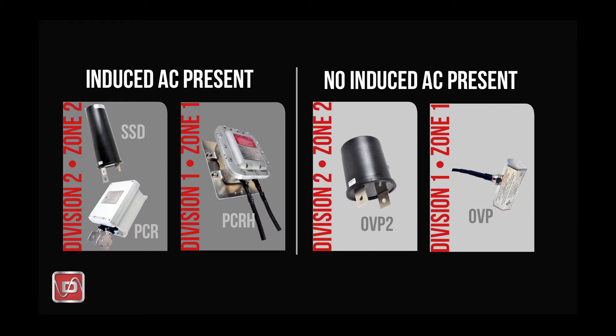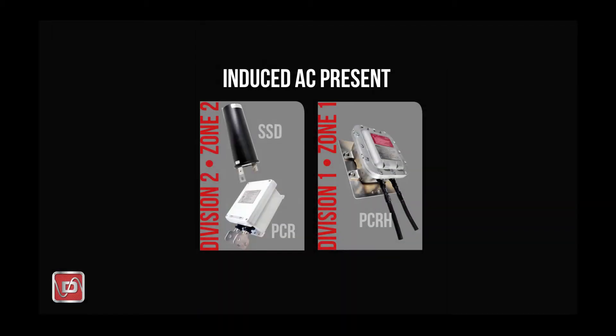In the first set of boxes, we have products that are suitable for use in locations where induced AC voltage is present. The second set contains products for use where AC induction is not present. Breaking them down further, we've grouped these products based on their hazardous location rating. The first grouping shows products able to address steady-state induced AC current. The general rule of thumb is to consider if there is measurable induced AC present now, or if it's likely to be present in the future. If so, choose a product in this first grouping such as the SSD, PCR, or PCRH, all of which are appropriately configured to handle steady-state AC.